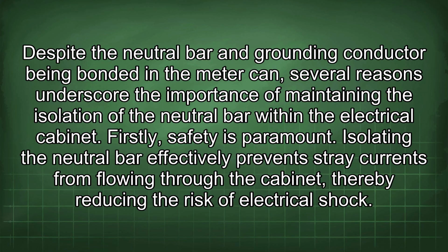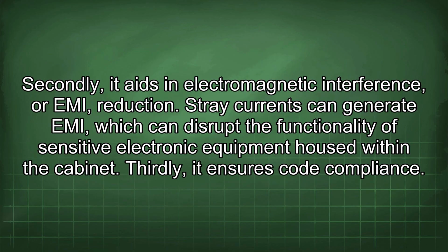Despite the neutral bar and grounding conductor being bonded in the meter can, several reasons underscore the importance of maintaining the isolation of the neutral bar within the electrical cabinet. Firstly, safety is paramount. Isolating the neutral bar effectively prevents stray currents from flowing through the cabinet, thereby reducing the risk of electrical shock. Secondly, it aids in electromagnetic interference, or EMI, reduction. Stray currents can generate EMI, which can disrupt the functionality of sensitive electronic equipment housed within the cabinet.